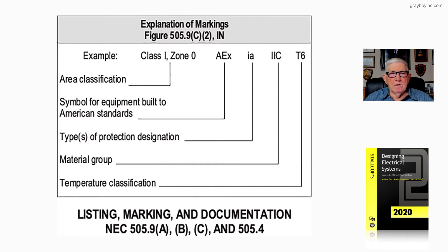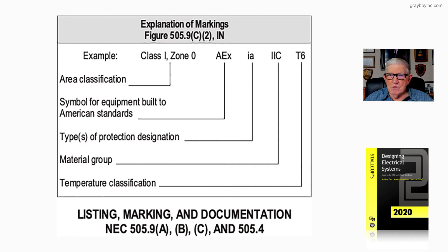Notice we have the example, and this is the area of classification — it's Class 1, Zone 0. The vapors are present there for a thousand hours or more, but we can put this equipment in a Class 1, Zone 0 area.